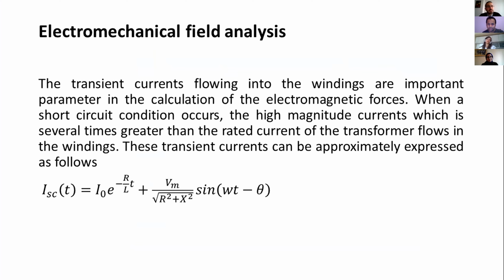I was talking about the electromechanical field analysis. As I said, the transient currents flowing into windings are an important parameter in the calculation of the electromagnetic forces. When a short circuit condition occurs, high magnitude currents, several times greater than the rated current of the transformer, flow into the winding. These transient currents can be approximately expressed as follows. In this equation, R, X, and L are resistance, reactance, and inductance respectively.